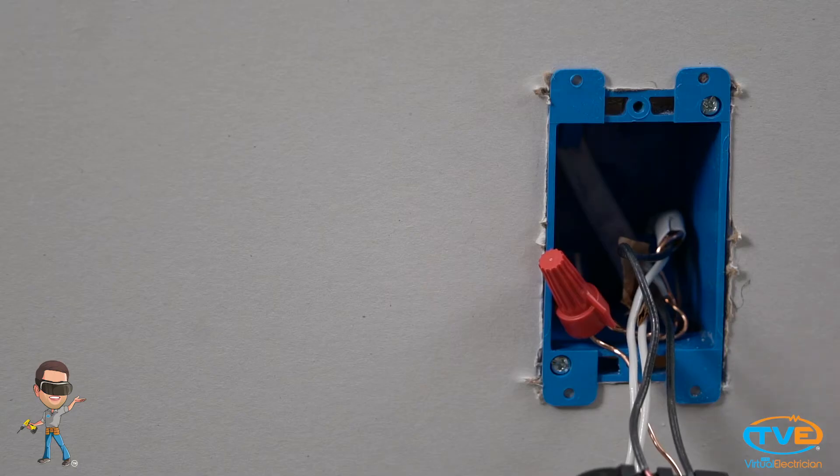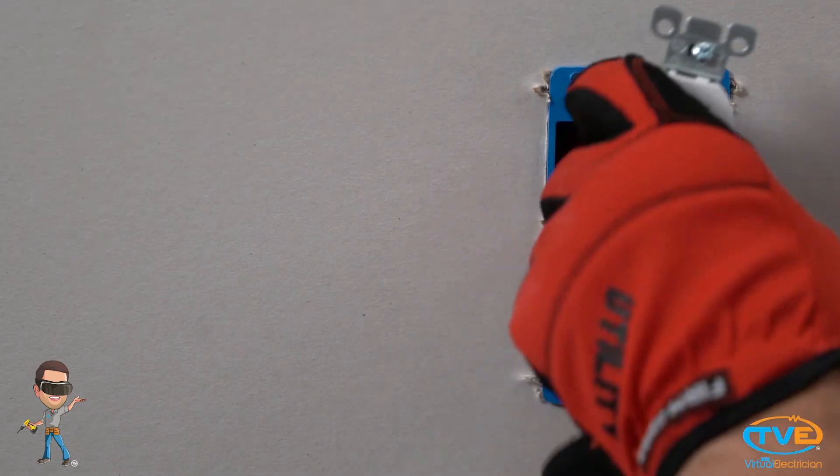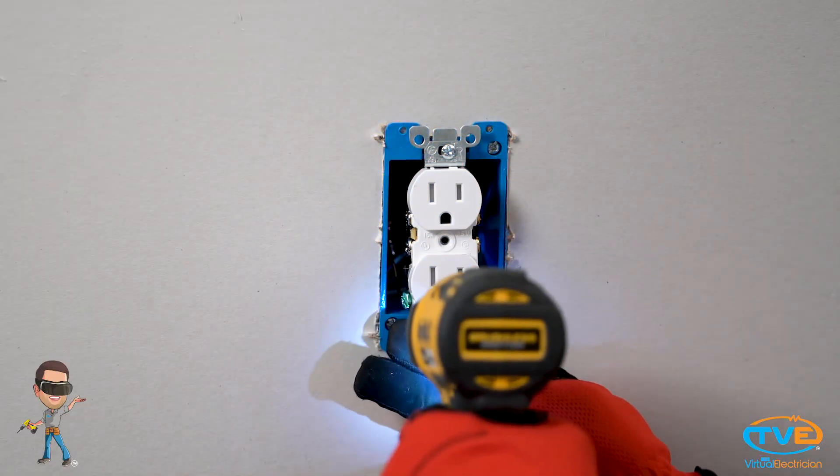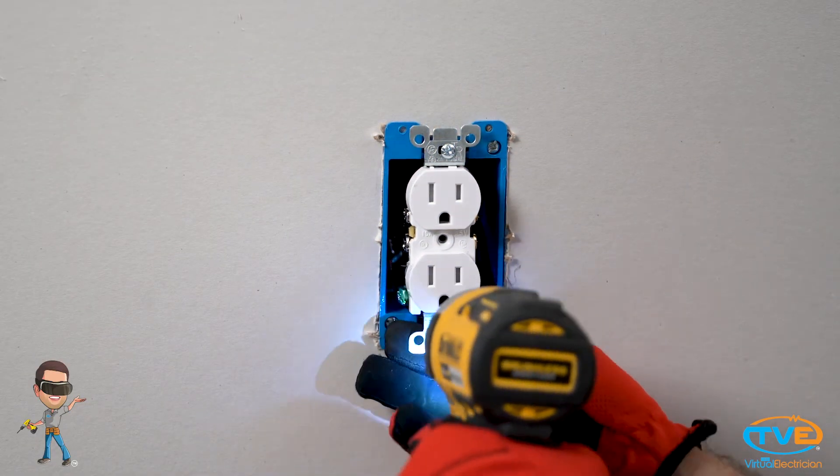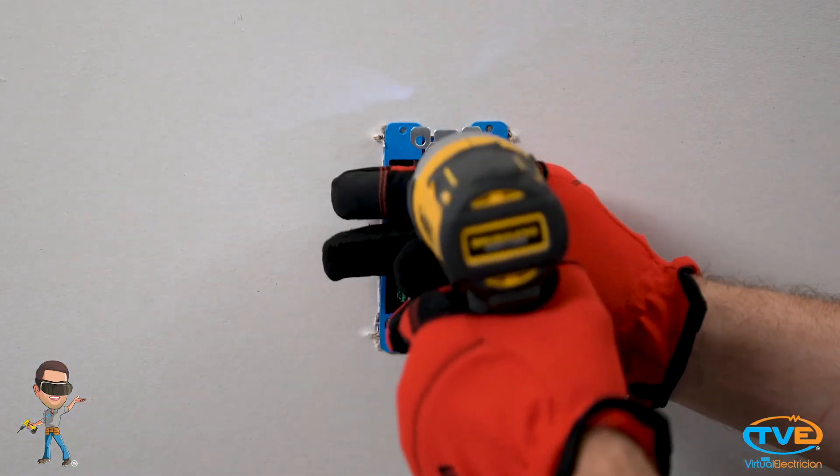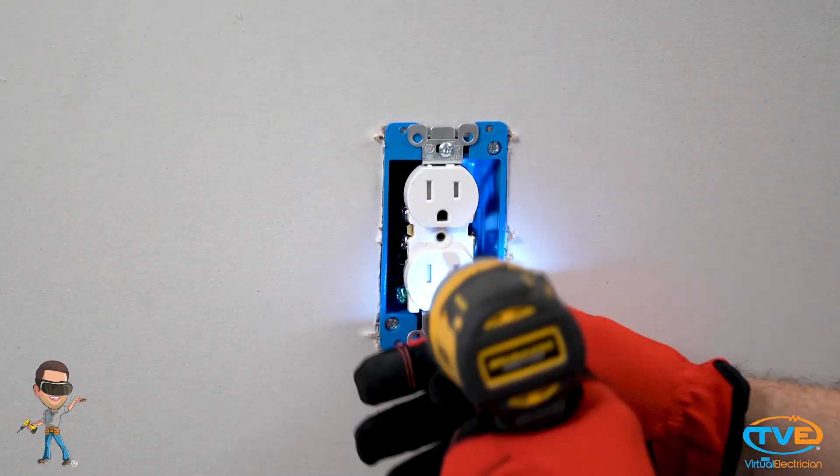Now you just screw the outlet in. Put your finger down on the wires and make an S shape as you push the wires back in the box. The ears on here are to help you get the outlet flush with the box. The ears should be flat against the box and leave enough slack on the screw where you can tap the outlet with your screwdriver to make it straight.